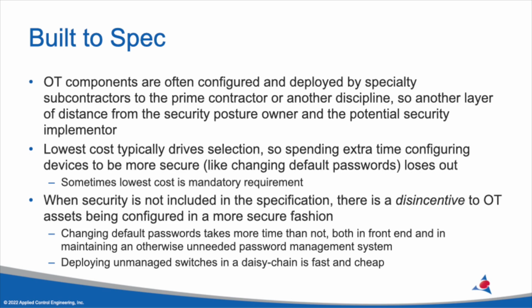And it's not just the time it takes to change that password. If I'm not doing anything, I'm not creating more work for myself. But if I decide I need to change the default passwords on all 20 HVAC controllers, that means I've got to change them — maybe not that long, but now I have to manage a KeePass database for a customer. Then I have to teach everyone else in the office how to use that, teach the technicians how to do it, make sure they have it on their laptop, and make sure they can access the database at 2 a.m. when they're on a service call and need to get into the system to troubleshoot why something's not turning on or why it's giving the wrong indication.